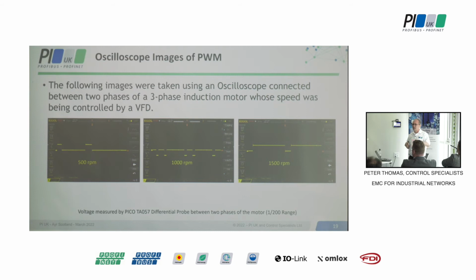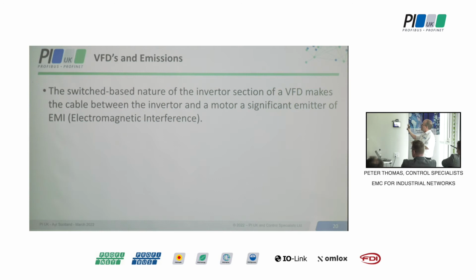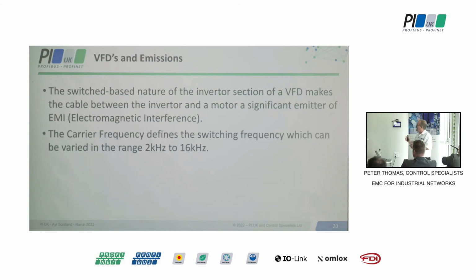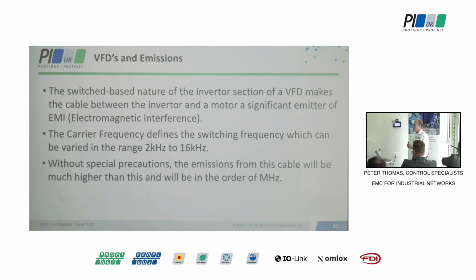Siemens, ABB, Danfoss, they know all about this, and they go into detail of how to limit the effect of this in its environment. The switch-based nature of the inverter section of a drive makes the cable between the inverter and the motor a significant emitter of EMI. This carrier frequency, which can be varied in that range, is the bit that's going to cause us a problem. Without special precautions, the emissions from this cable are going to be much higher, in the order of megahertz, not kilohertz.